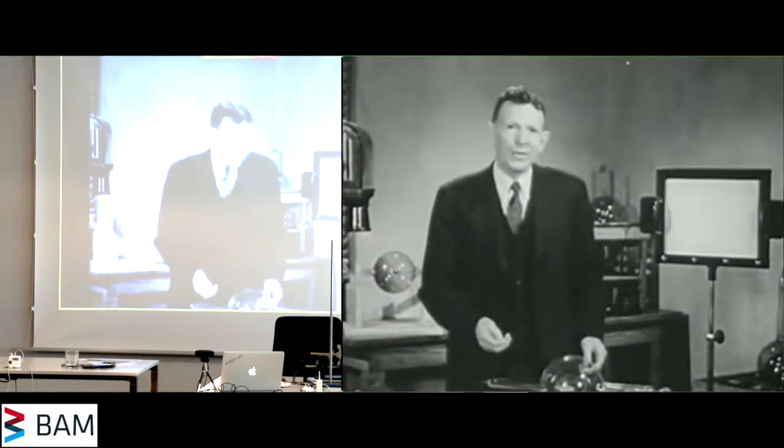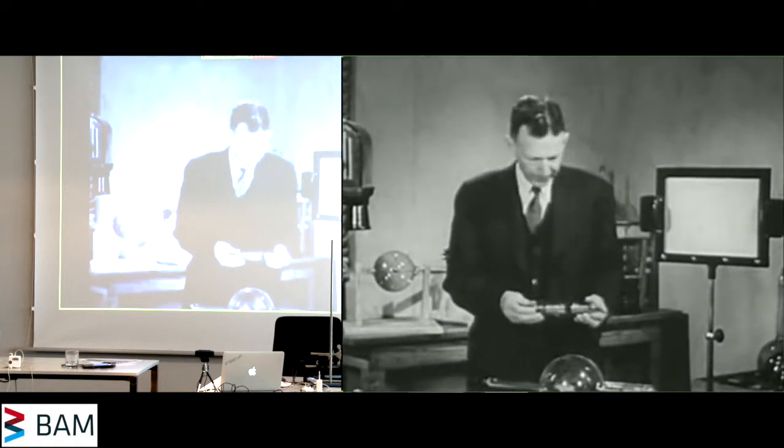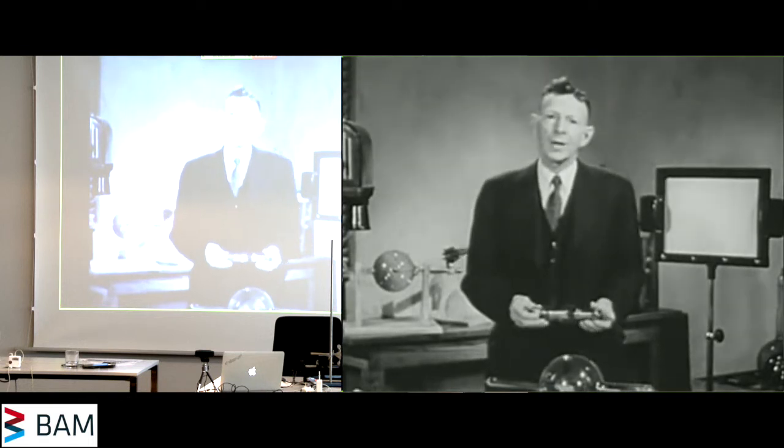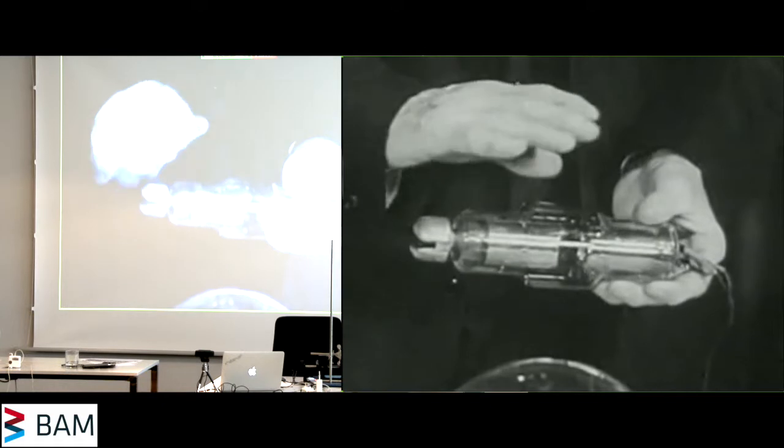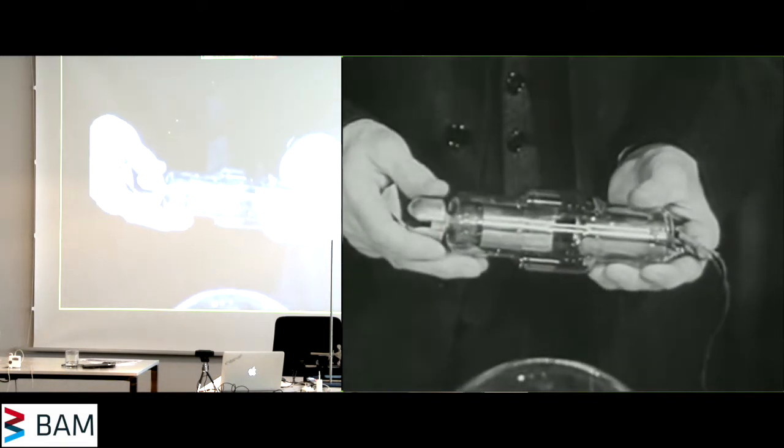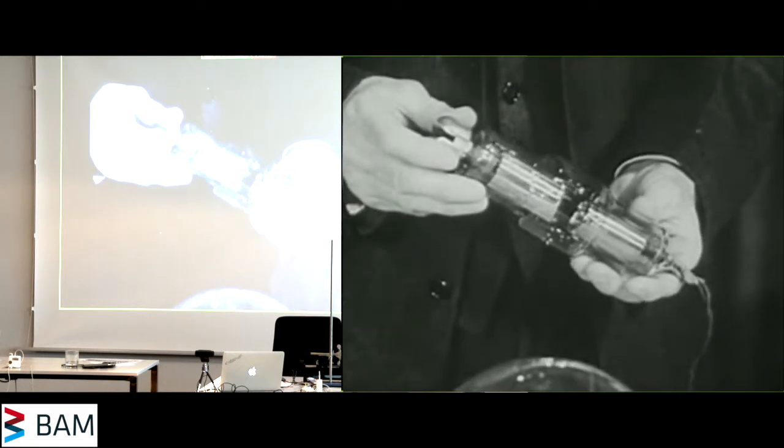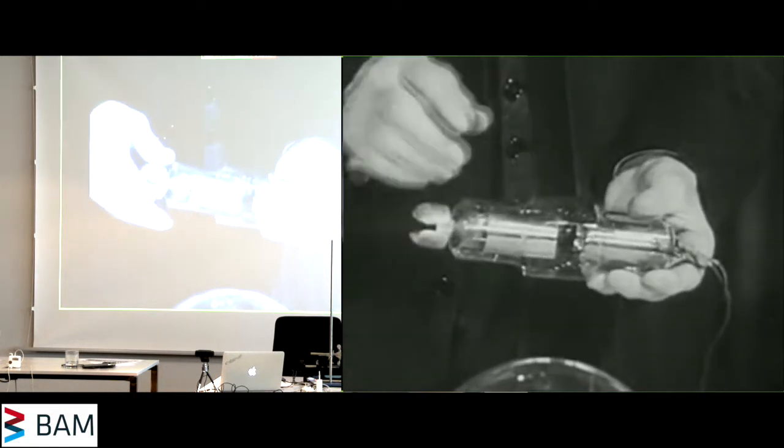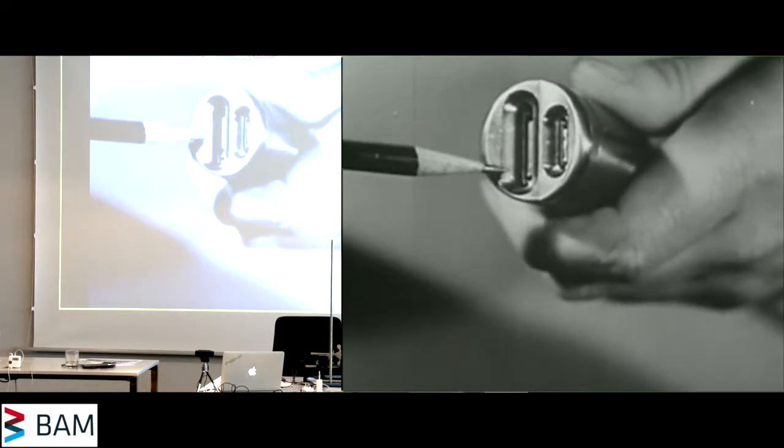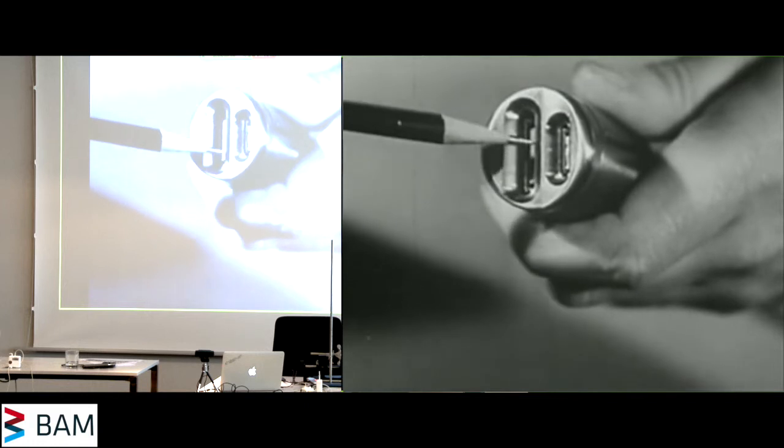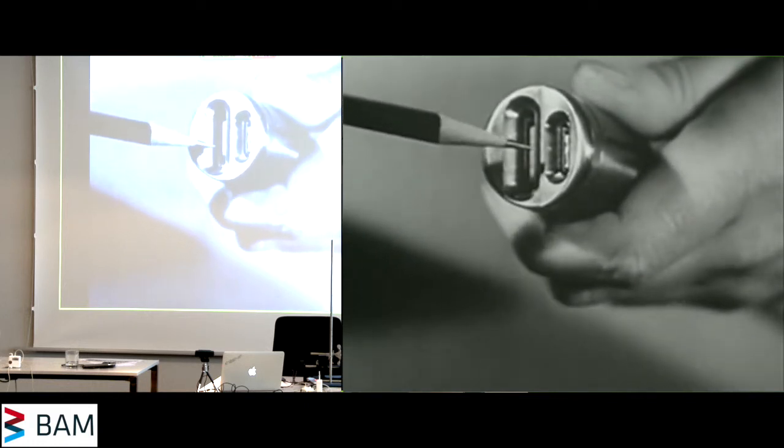In the present day hot cathode x-ray tube, of which this is one of several different types, there is a high vacuum. And the production of electrons depends only on the size and temperature of an incandescent tungsten filament with a cup-shaped structure surrounding it. This particular tube has two filaments, either of which may be used.